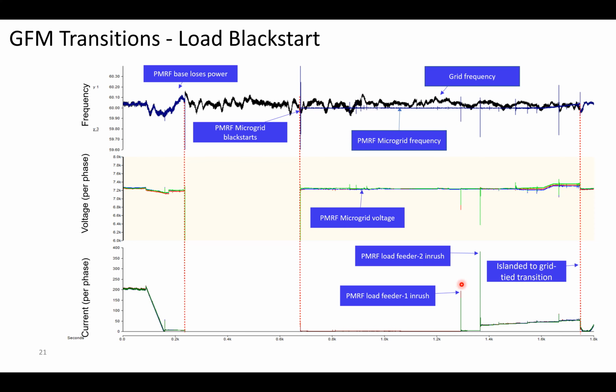And then we sequentially close the PMRF load feeder. So here you can see the inrush for each of those load feeders closing in. So that's the first feeder. And then we energize the second feeder, bring back the base, resume power to them. And then at the end, right over here, we initiated planned islanded back to grid tied to resume normal operation.